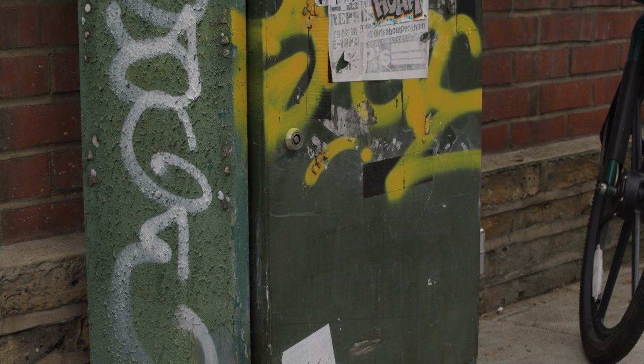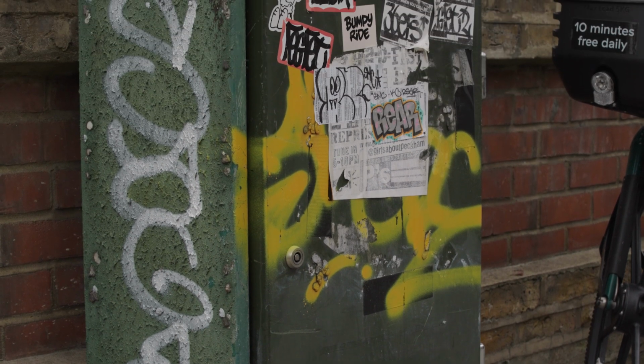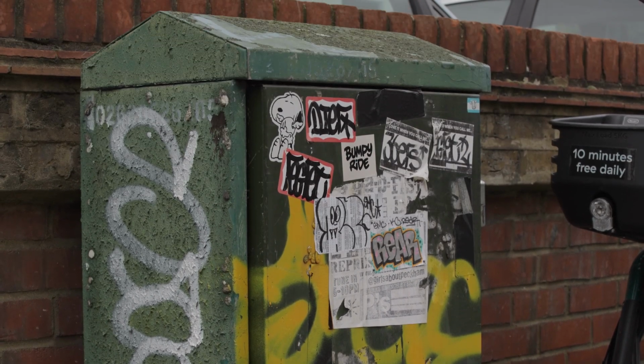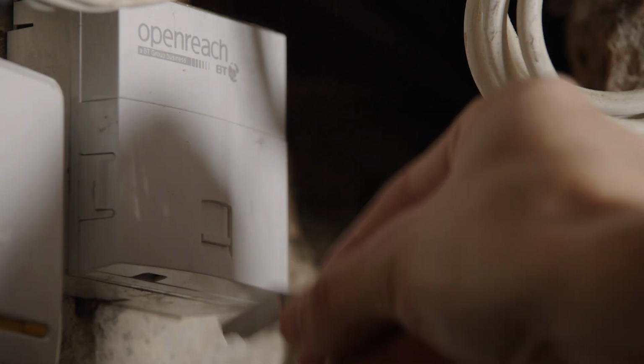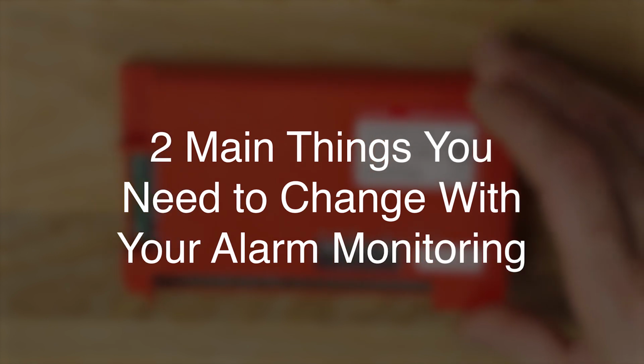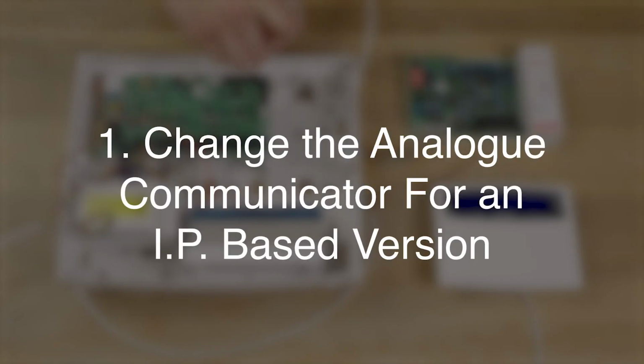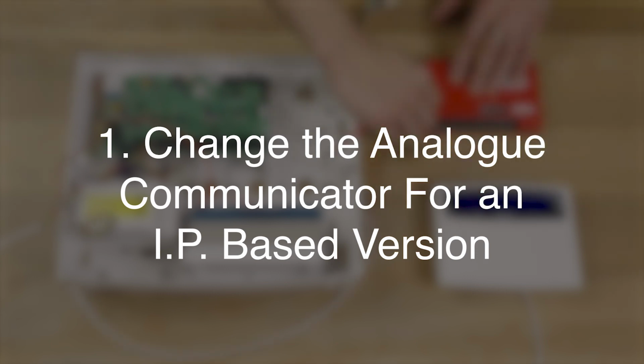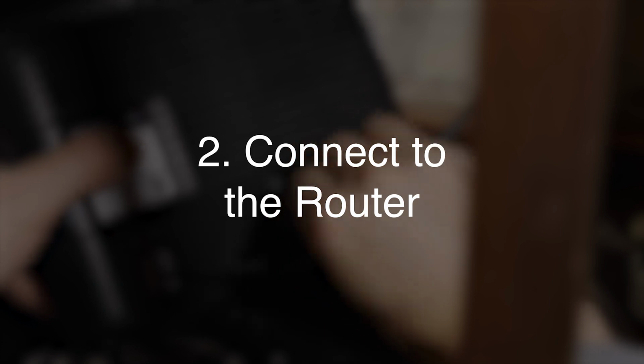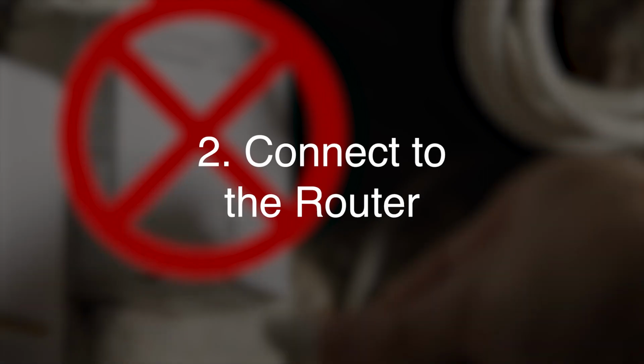If your telephone exchange has been upgraded from an old PSTN exchange to an IP system, you will need to change and upgrade your alarm monitoring service. The main two differences in changing from PSTN to IP are: 1. You need to change the digital communicator for an IP-based communicator, like the CSL DualCom or AMCO's LiveTalk. 2. You need to connect your communicator back to your internet router rather than your old PSTN telephone line.